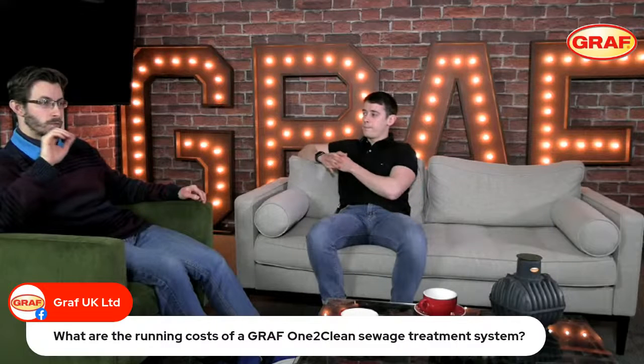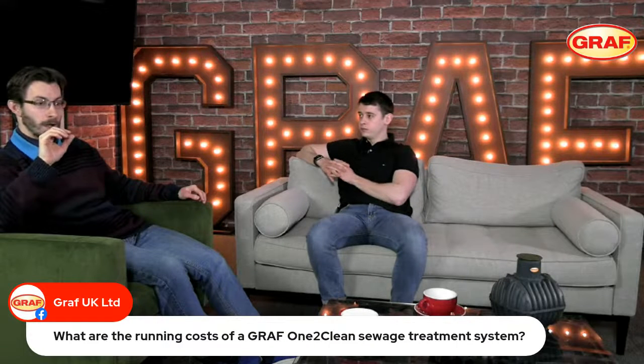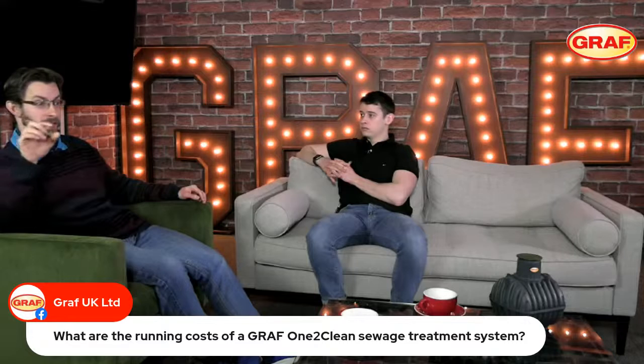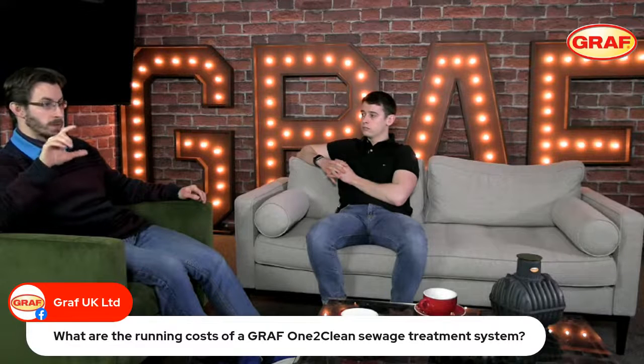But on the domestic side of things, it is very, very cheap to run. With the Graf systems, we talk about sequencing batch reactors, so SBR systems. So we're getting the control panel to run the compressor at set intervals per day. Whereas most other treatment systems on the market will run the compressor pretty much 24/7, with the Graf systems we generally run it between 8 and 12 hours a day, depending on the population size.